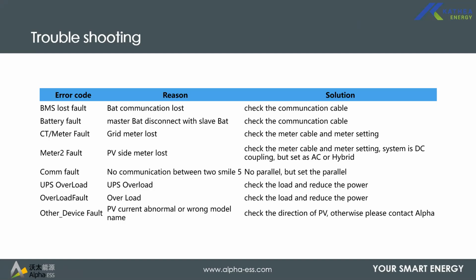That's why we even discourage connecting things like the pool pump on the backup. When the pump starts, it spikes and exceeds 5 kilowatts, and then the inverter trips on an overload fault. So I thought that was a fault we should mention that we come across. Thanks. You can continue, Brian. It's okay.